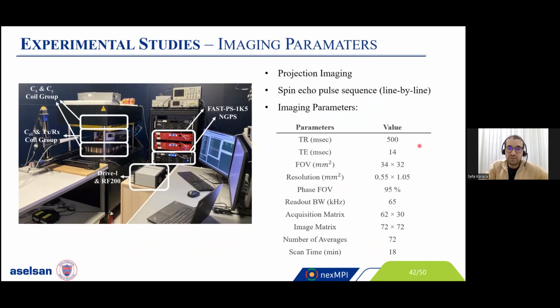So for the experimental imaging studies, we perform projection imaging. Again, because of the higher field inhomogeneity, we perform spin echo pulse sequences. You can see our imaging parameters in here. Our scan time is around 18 minutes. This is because we perform low field MRI and we try to go with a higher number of averages, and this increases our scanning time.